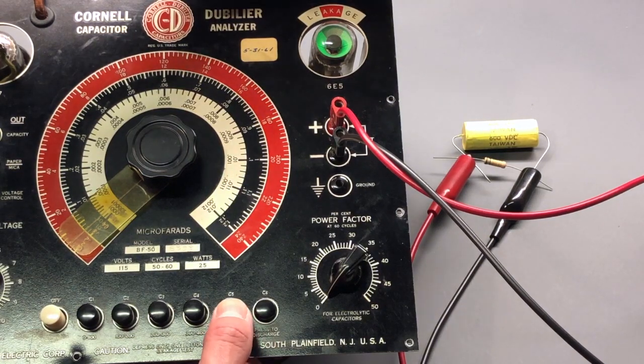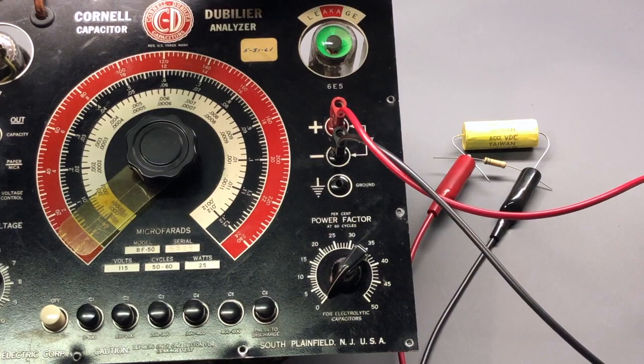And we'll start the test like so. So you can see it quickly closes, and it looks like it's remaining closed, which is correct. And there it popped open and then closed very quickly. And you can see now that's beginning to repeat. So again, when that eye closes together, that shows very high leakage current, and then the frequency of how often that opens and closes, or again, the manual refers to that as the eye flashing. You can use that to determine what the resistance would be.